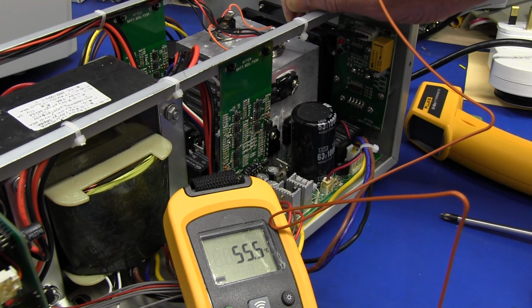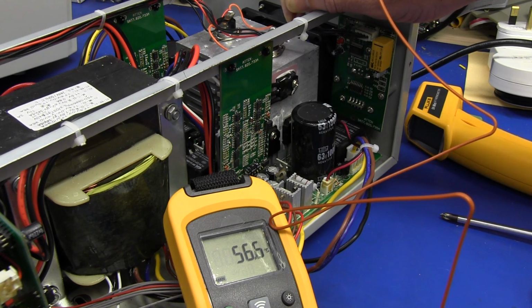So before, what we saw with 65 degrees C was the worst case design scenario, worst case load scenario, really, pretty much. Although we could check all the taps and the various margins on all the taps, but geez, don't want to gild the lily, just want to get a ballpark. So yeah, that seems to be operating at quite a safe temperature, so pretty happy with that. Pretty well designed. They do know what they're doing with the multiple taps. I'm sure they've done their calculations and their thermal tests and measurements and all that sort of stuff, and for good measure they've put in the thermal cutout as well for any thermal failures with thermal runaway and things like that. So nice work.